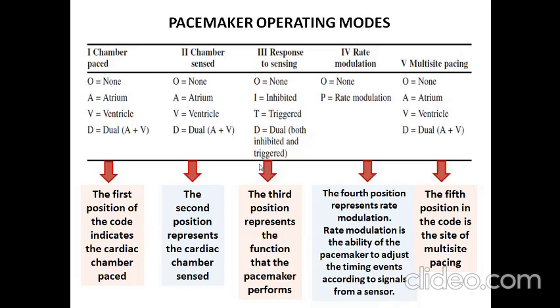The fourth letter represents rate modulation, given with the letter R. Rate modulation is the ability of the pacemaker to adjust the timing of events according to signals from the sensor. The fifth letter is actually an additional option. It indicates the site of multi-site pacing, whether we are applying multi-site pacing or not. So these are the pacemaker operating mode representations.